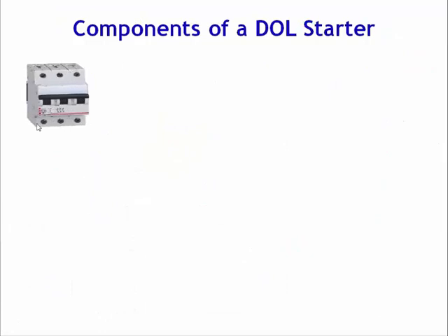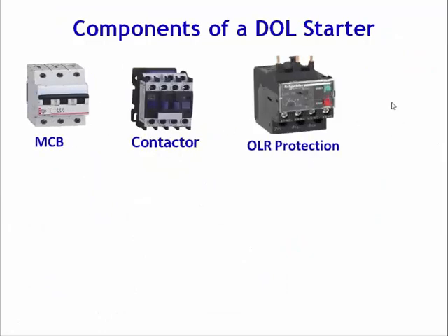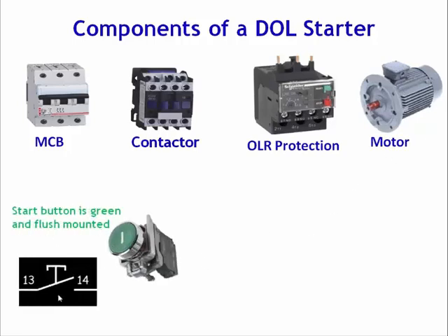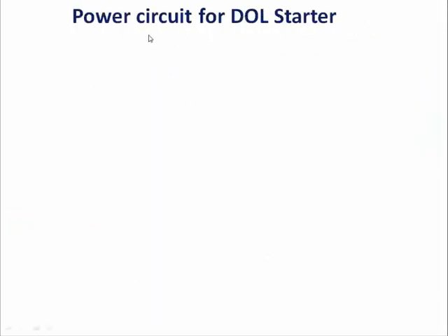So first let's start with the components of DOL starter. The components used in a DOL starter are: MCB, contactor, overload protection relay, motor, start push button in green color with NO contact, and one NC contact with stop push button in red color.